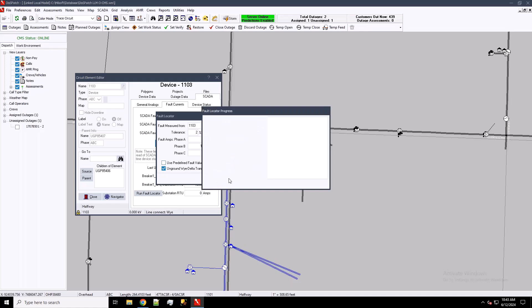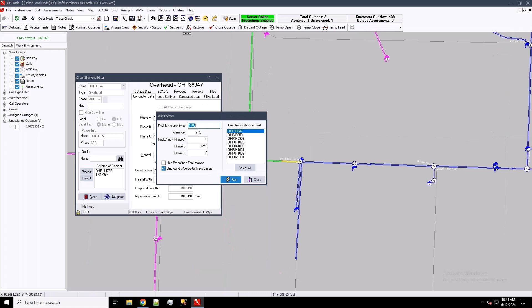And when I run fault locator, I'll just click the run button here. That's basically going to do a fault current analysis from that selected device downstream and try to identify where we could possibly have measured that fault value that we received back from SCADA. I'm going to zoom out a little bit. So these results, you'll see, are just simply listed here.